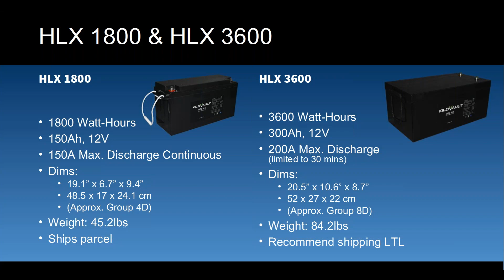And the only other thing I really want to highlight about the specs is, again, that high charge and discharge current, which is really important these days, especially when we're talking about AC coupling applications or residential storage, where you typically have a really large solar array and a fairly modestly sized battery bank, just sized for the critical loads. The batteries can handle that charge current from the entire array without issue. With lead acid batteries, you oftentimes have to be pretty concerned with the charge rate, not putting too much current into them at a given time and potentially reducing their lifespan.